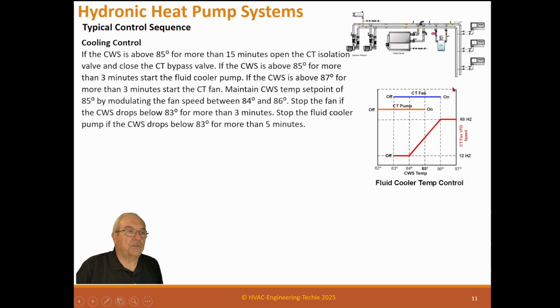All right, cooling control. If the condenser water supply is above 85 degrees for more than 15 minutes, open the cooling tower isolation valve and close the cooling tower bypass valve. If the condenser water is above 85 degrees for more than 3 minutes, start the fluid cooler pump. If the condenser water is above 87 degrees for more than 3 minutes, start the cooling tower fan.